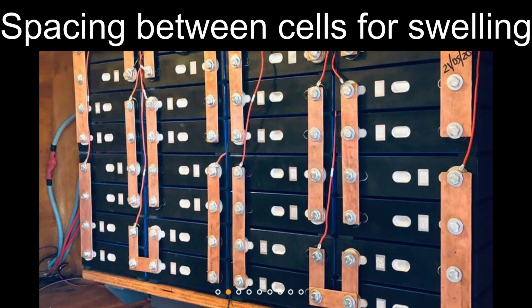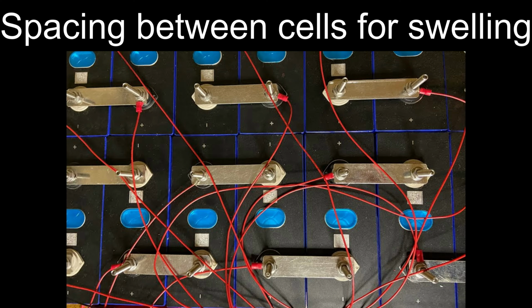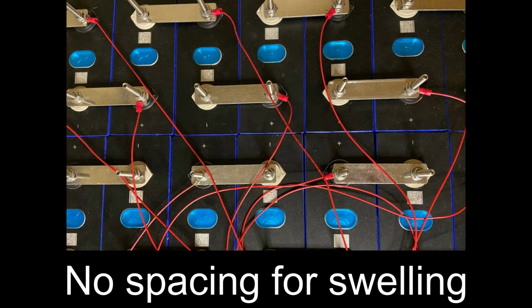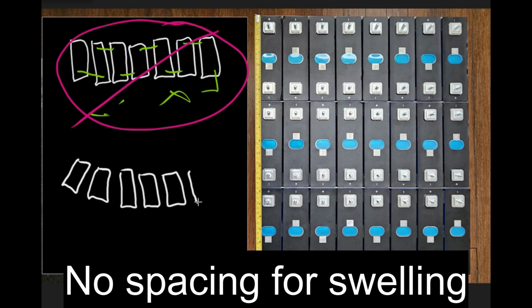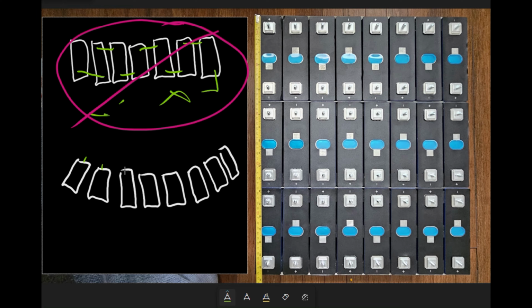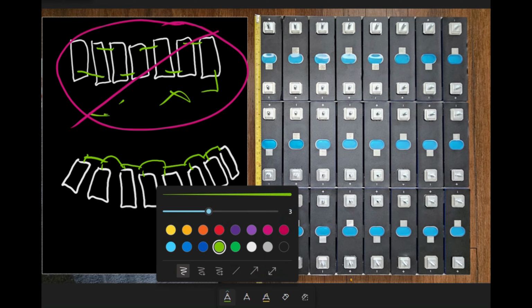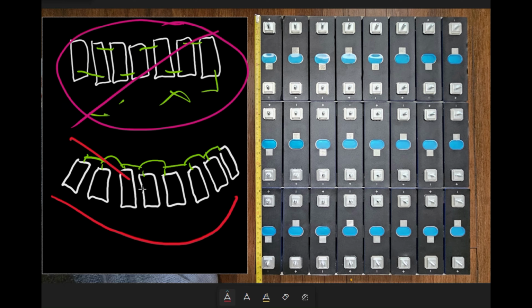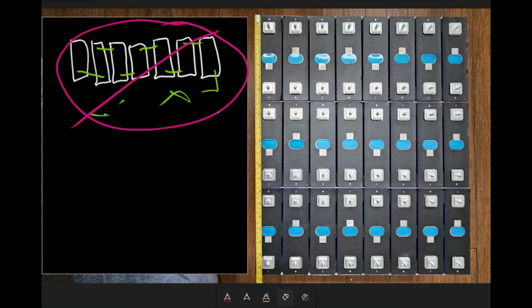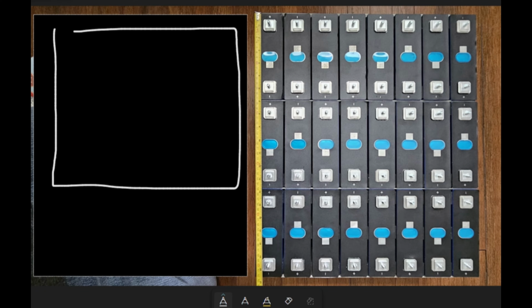Also in the early days of LiPo, they used very rigid bus bars on top, like 1/4 inch or 1/2 inch plate, copper or various metals, aluminum. So when the batteries swelled up, even after compression, all the stress was on the top of those bus bars and on the terminals, causing battery failure after the terminals pried away from each other during swelling.